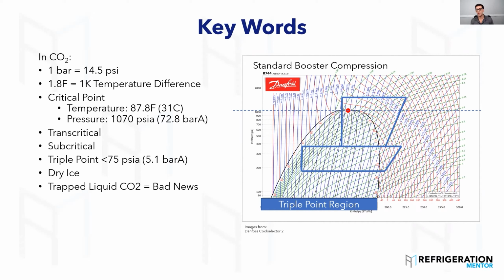Trapped liquid. This is really bad. You do not want to do this. At 68 degrees Fahrenheit or 20 degrees Celsius, you're looking at about 868 PSI pressure in a cylinder, we'll say. If all of a sudden you bring that temperature up by 1 degree Celsius, 1.8 Fahrenheit, it expands by 10 times. So you're going to see a massive amount of pressure increase. That's why you never want to trap CO2. You'll see along a lot of ball valves and such, there'll be check valves around them to make sure you don't trap CO2, because it is dangerous when you do that. Any questions so far?